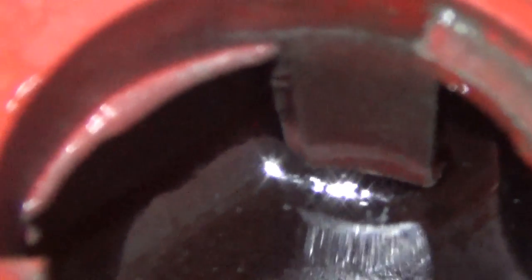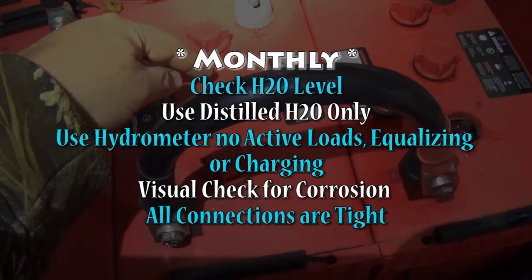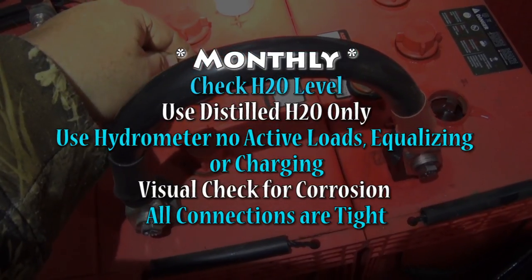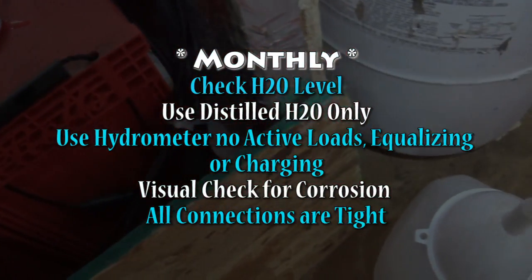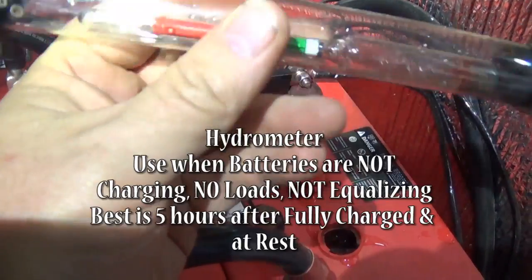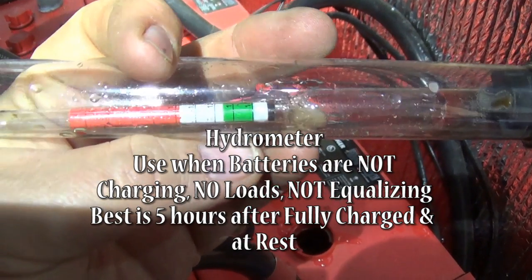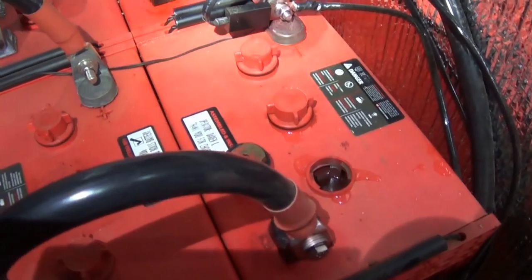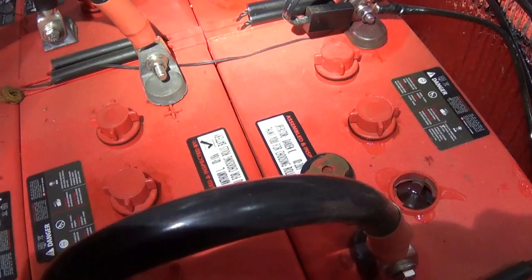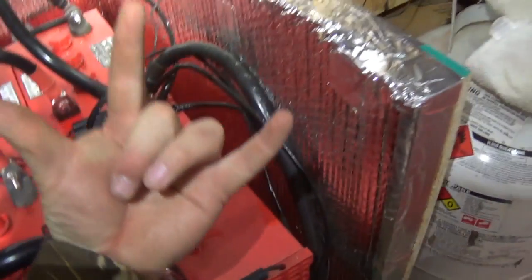I'm going to do that now to all my cells and then we should be good to go. This video is just to let you know: check the water on your batteries every single month. I have not been good about that — that's why that one was so low. Once fully charged and at rest, that's when you break out this acid-testing device — I'll put it in the description — and test the acid in your battery. That tells you how good the battery actually is based on the green, yellow, and red indicators. Do this on a monthly basis to maintain your batteries, because they are the heart and soul of your solar system. Thanks for watching — don't forget to like, subscribe, share, and comment!